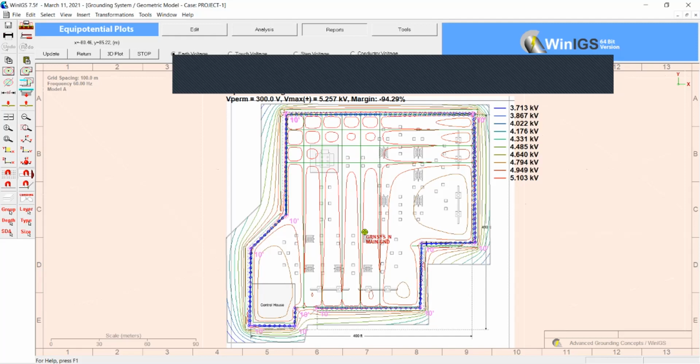Is there too much potential? Yes, the maximum potential is 5 kV. But this is showing you where you have how much potential. This is the earth voltage, because see the green circle here: if 5 kiloampere current is injected here, then this will be the gradient of the voltage surrounding my substations. You have to have it.